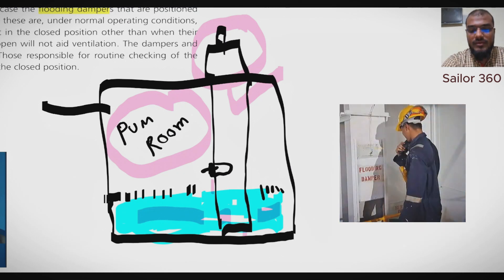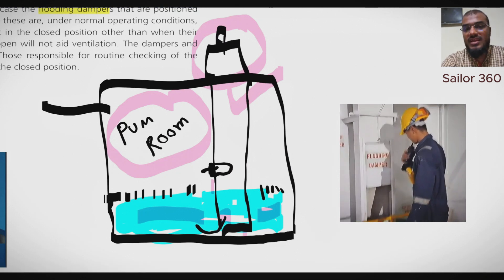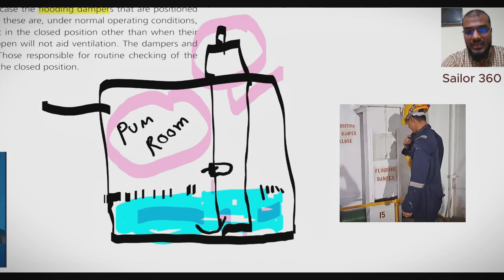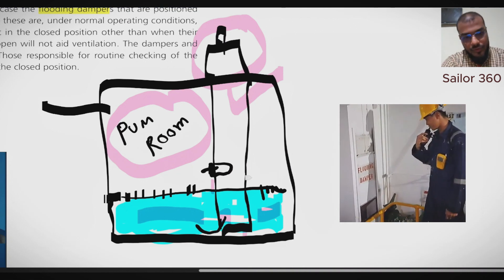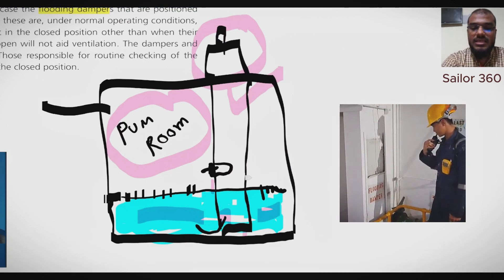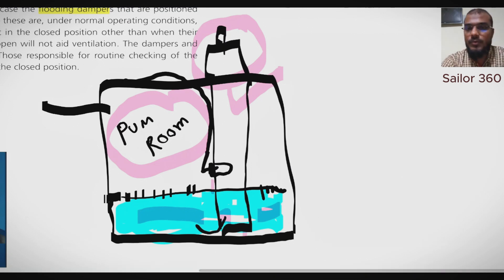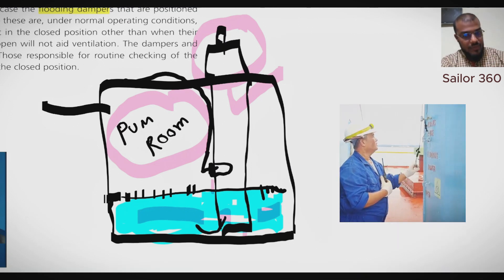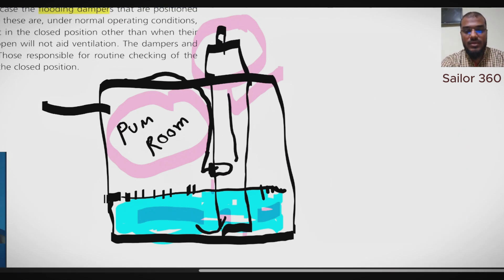The question is when to keep it closed and when to keep it open. We keep it closed during normal operation when we need air from the below part. We keep it open during flooding — if the lower part is already submerged by water, we can still continue ventilation using the flap. There is a connection from the flap all the way to the outside of the pump room so it can be controlled, opened, and closed from outside.